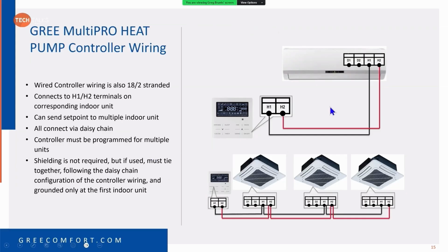Your H1 and H2 connections are for your wired controller. The wired controllers come factory set up for a 1-to-1 connection, in other words, one controller per indoor unit. Make sure you leave it that way if you have one indoor unit, because if you change that in the project settings, it's going to give you an error code. You can control up to 16 indoor units with one wired controller. It's done in a daisy chain fashion across H1 and H2, just like you would D1 and D2, only you're using H1 and H2 because those are your controller connections.